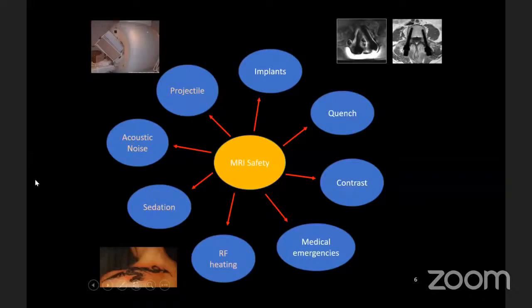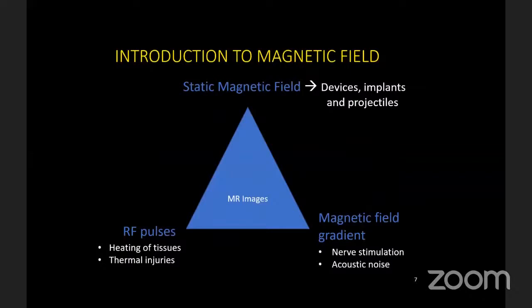Let me introduce the three different types of magnetic field effects. One is caused by the static magnetic field of the magnet, which gives rise to device and implant projectile injuries. Second would be the effects of radiofrequency pulses, which leads to heating of tissues and thermal injuries. And then there's the magnetic field gradient, which can cause nerve stimulation injuries or acoustic noise.